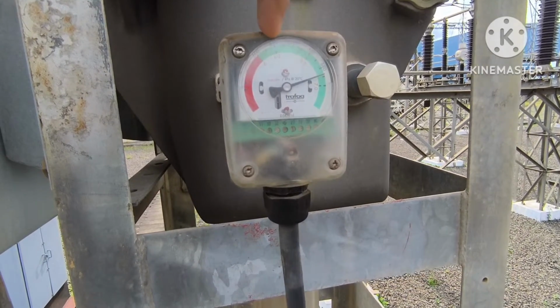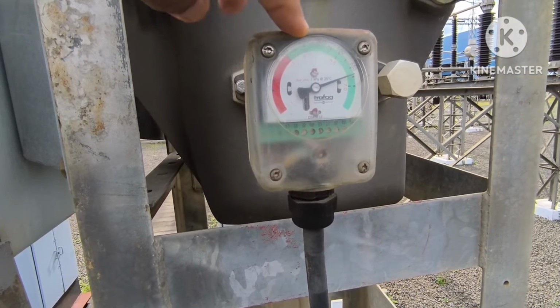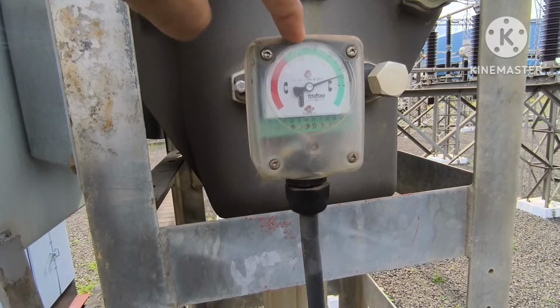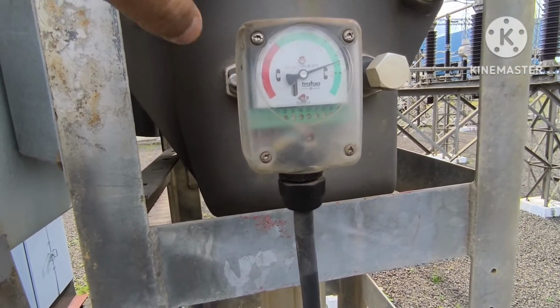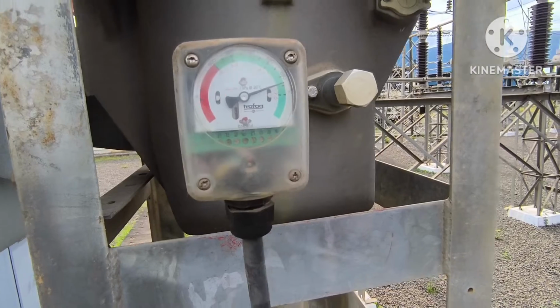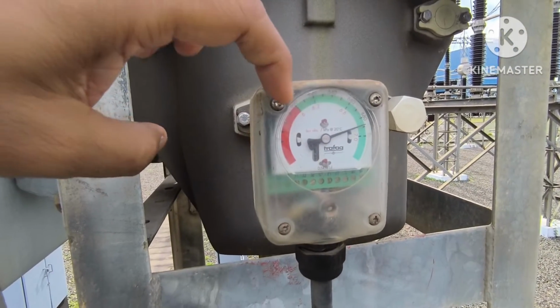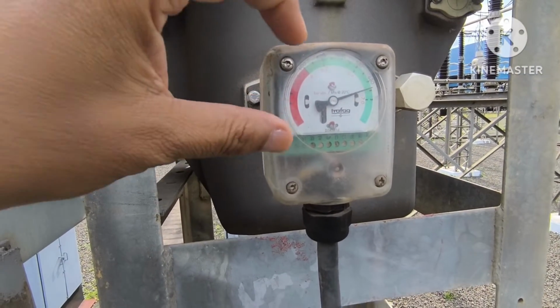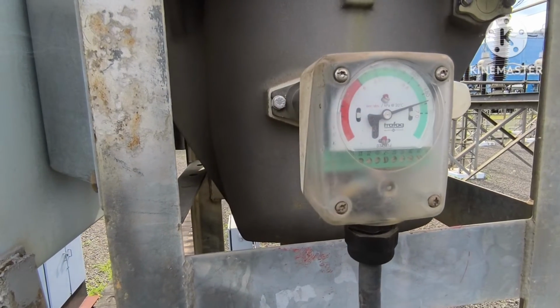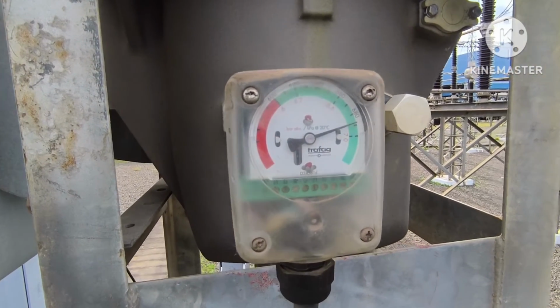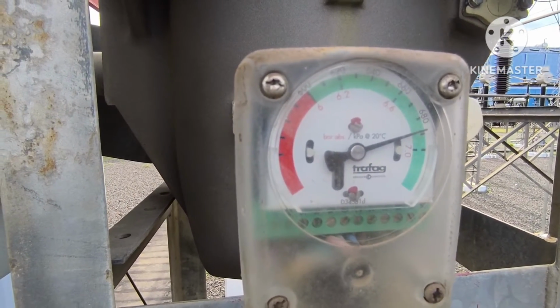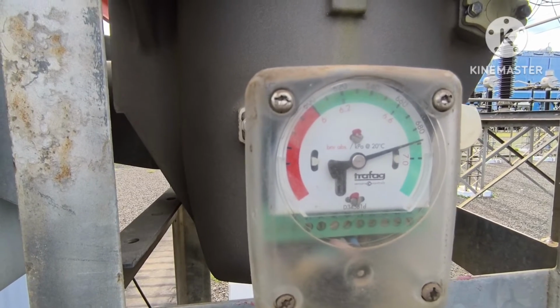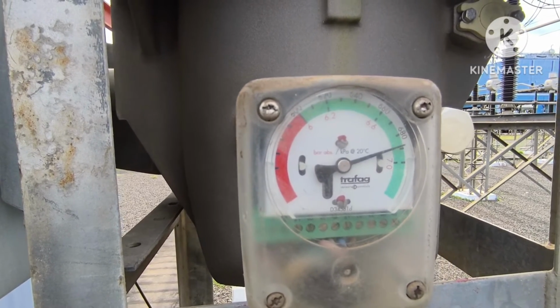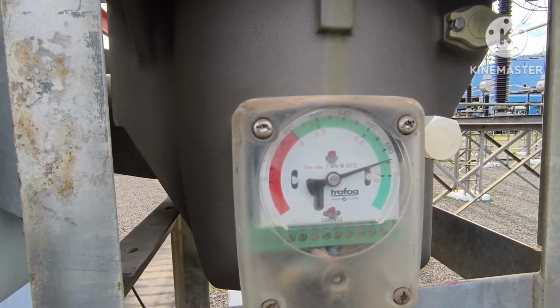Whenever the pressure reaches 6.2 bar, an alarm will come automatically. So we have to arrange for refilling of gas. At 6 the breaker will be locked out. This is the red zone. In this zone we cannot operate the breaker. Breaker operation is not possible in the red zone, below 6. 6 is the lockout pressure, 6.2 is the alarming pressure.